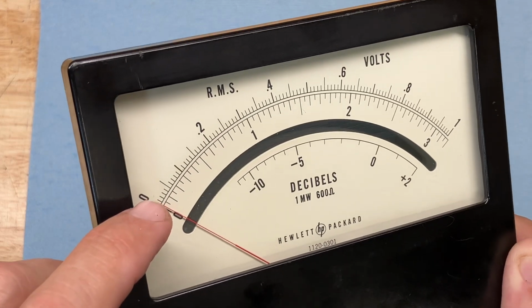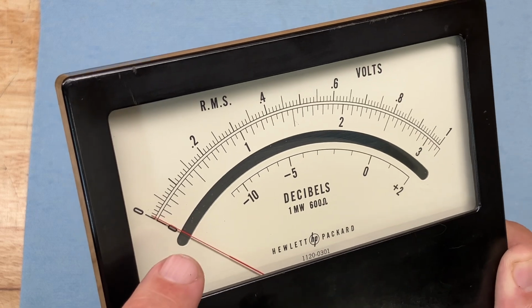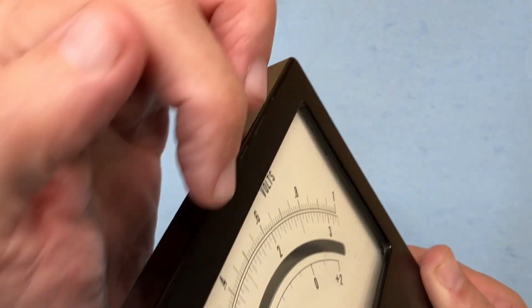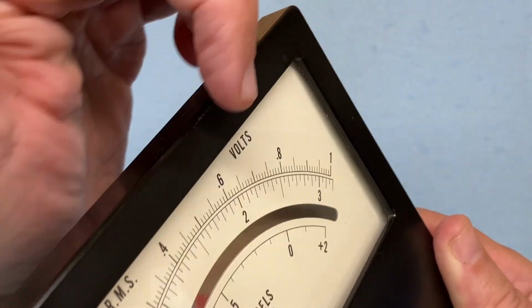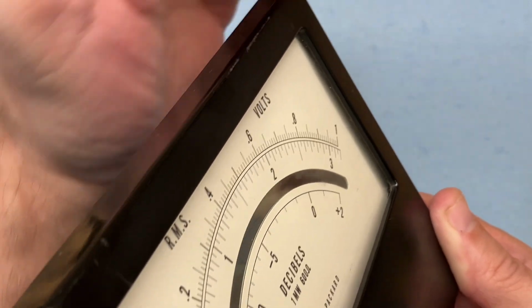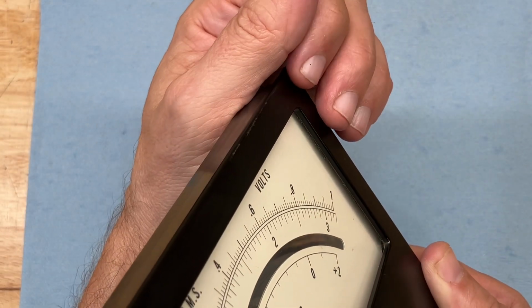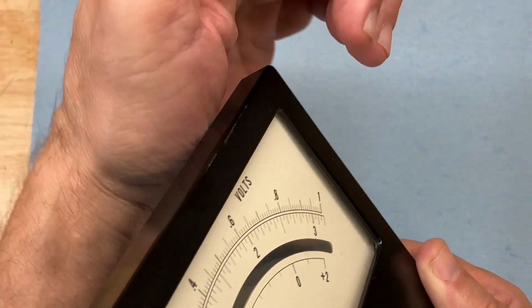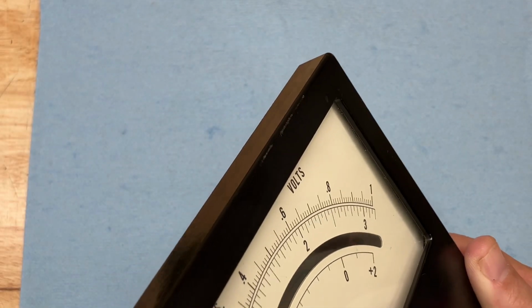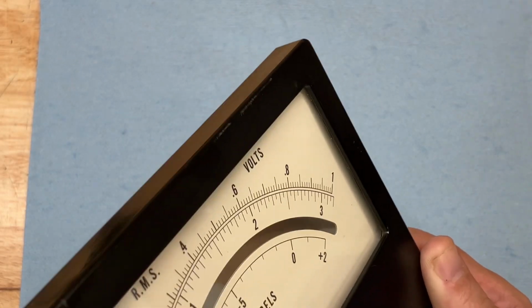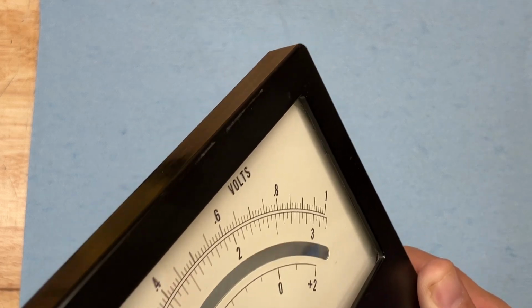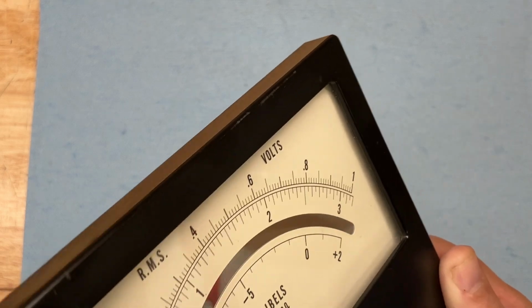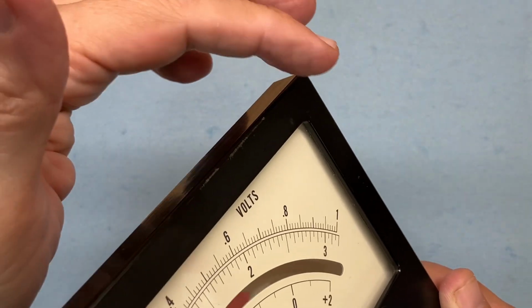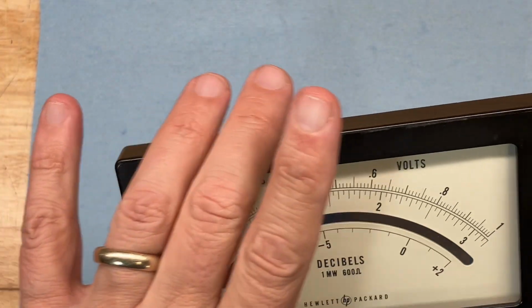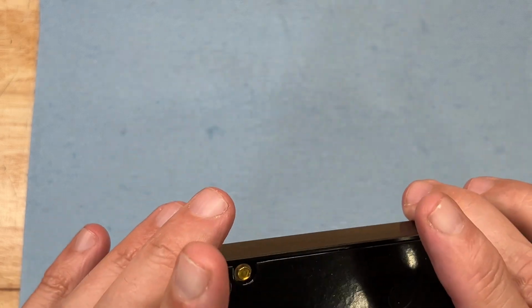Now it seems like the needle itself is not actually bent, but the white face of the meter with the graduations on it seems to be slightly warped in this upper right corner, so that the needle hits that face near the 1 and gets stuck there. If you tap it, it comes back, but if you don't tap it, it stays where it last landed. So I'm going to see if I can open it up and maybe coax this back into its correct position without messing anything up. It's going to be a tricky operation, but I can try it anyway.